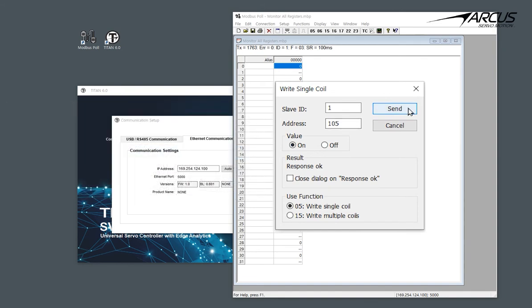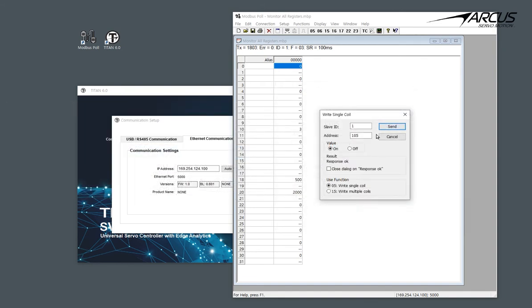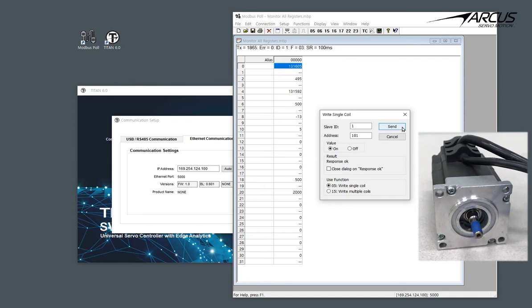With the servo on, let's do some jogging commands. We know that coil 101 is jog plus, so let's jog the motor in the positive direction by turning on coil 101. We can see that the motor is jogging and the encoder register shows the encoder counter. We can stop by turning off the coil 101.